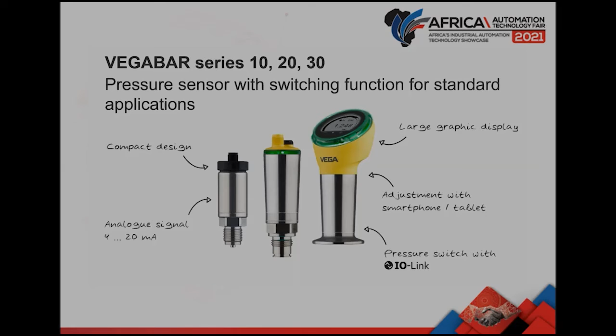Some other features built into these devices is IO-Link protocol. So for the factory automation plants, this is very suitable, as IO-Link is a preferred protocol to be used with high-speed updating, and it's suitable for fast applications. And these are equipped with Bluetooth as well. So the VEGABAR 20 and 30 series doesn't require the HART protocol anymore for remote connection and configuration. All this is done by Bluetooth, where you use your smartphone or tablet to do complete configuration and setup.